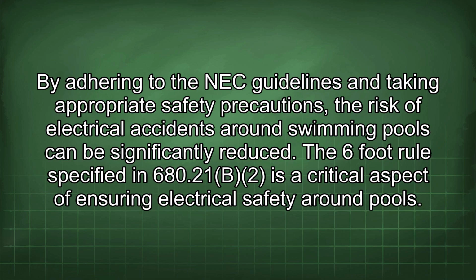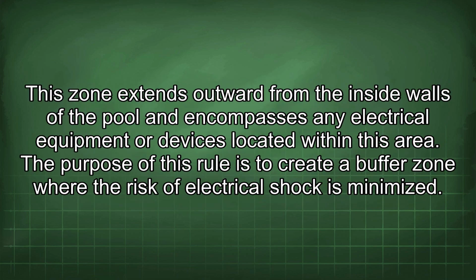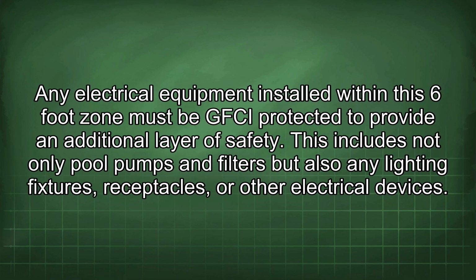The 6-foot rule specified in 680.21(B)(2) is a critical aspect of ensuring electrical safety around pools. This zone extends outward from the inside walls of the pool and encompasses any electrical equipment or devices located within this area. The purpose of this rule is to create a buffer zone where the risk of electrical shock is minimized. Any electrical equipment installed within the 6-foot zone must be GFCI protected to provide an additional layer of safety.